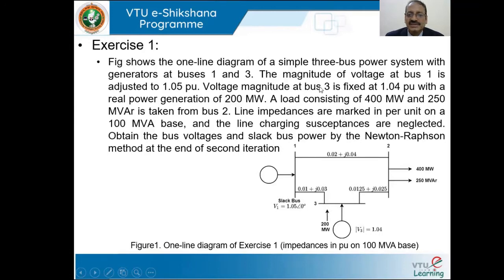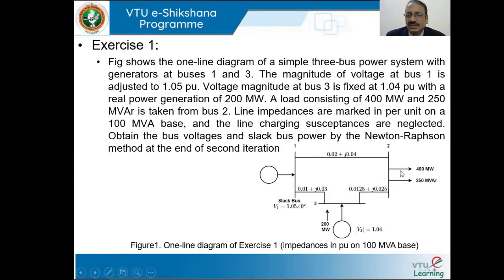Bus 1 is the slack bus where a generator is connected and its voltage is adjusted to V1 = 1.05 at angle 0. Voltage magnitude at bus 3 is fixed at 1.04 per unit — the generator excitation is adjusted such that bus 3 voltage can be maintained at 1.04 per unit. The real power generation of the generator connected to bus 3 is 200 megawatt.